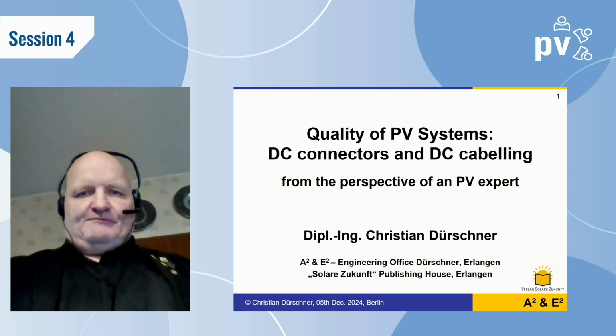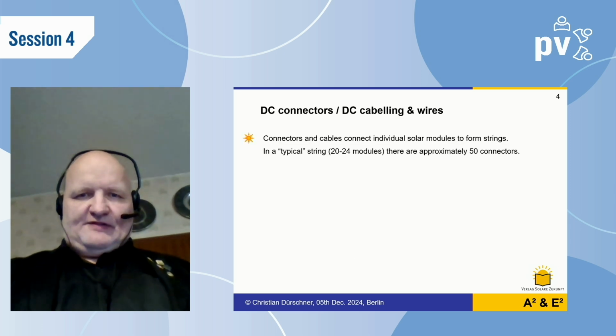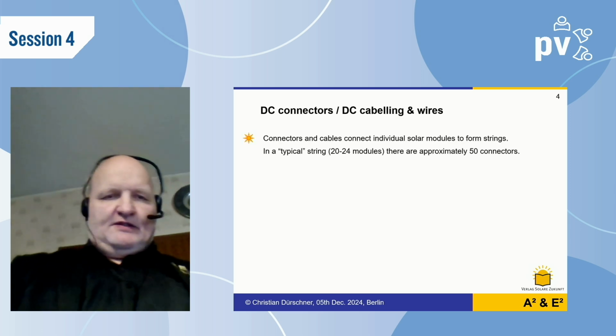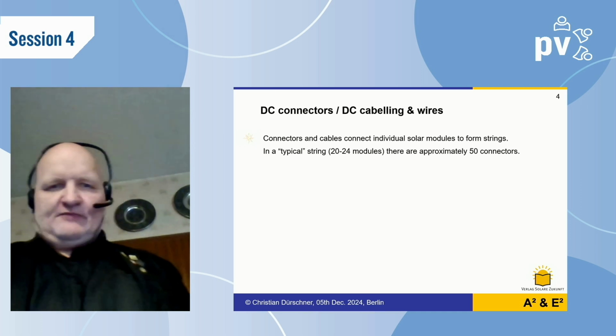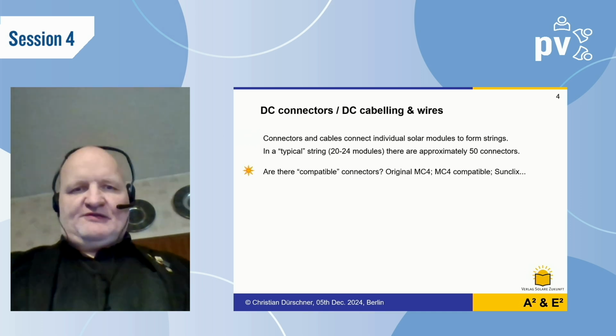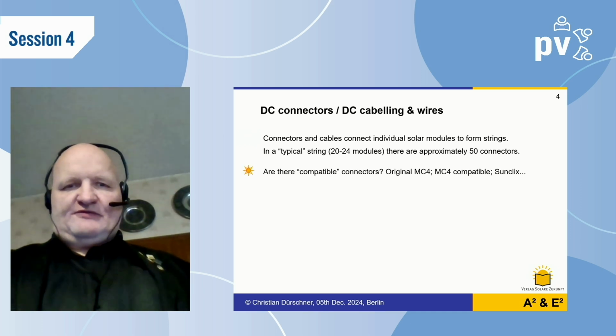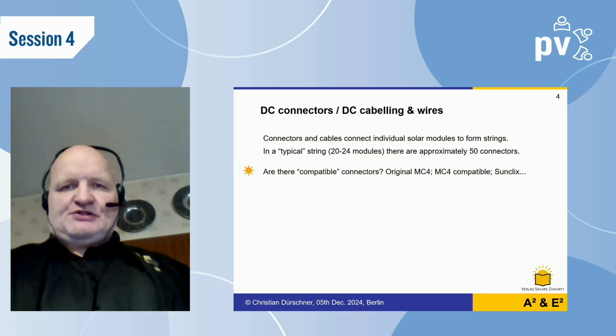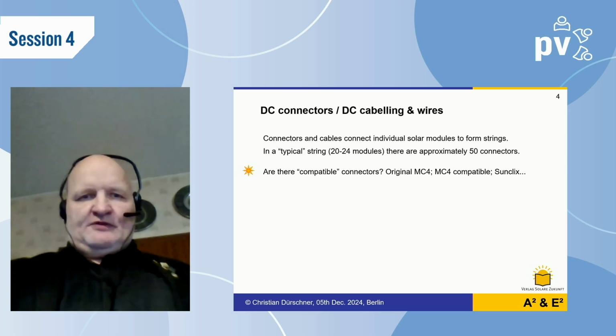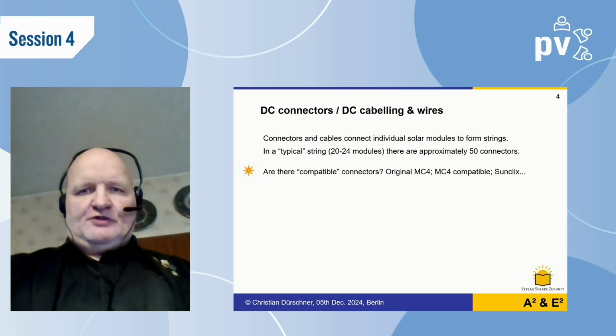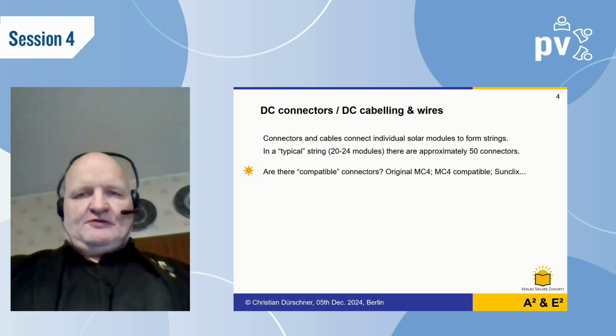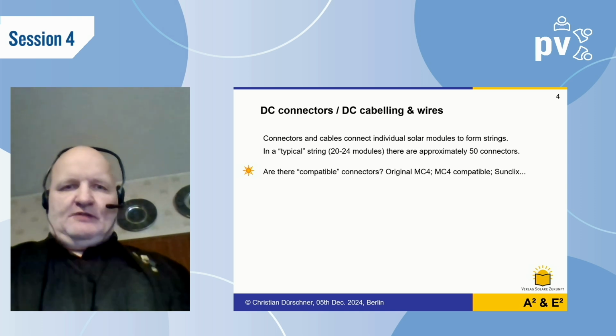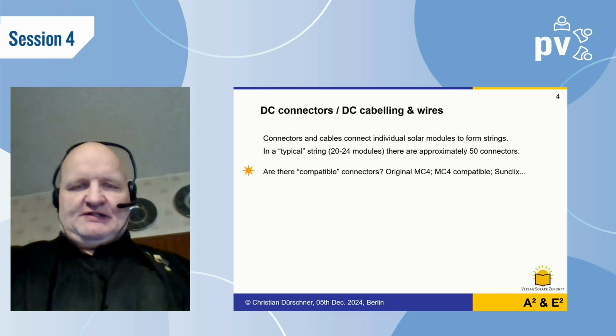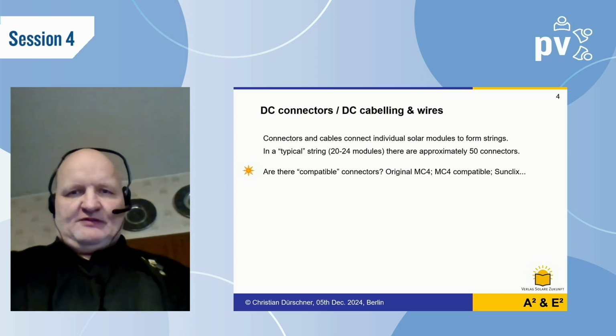Connectors are very often an issue in the system. Every module has two connectors, but the connection between modules is not the problem. The problem is the connection between the end of the string and the string wiring, and also on the other side, the string wiring to the inverter. There, the installer has to make his own crimping with the right connector, and what is the right connector we will see.